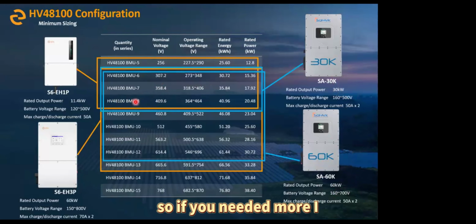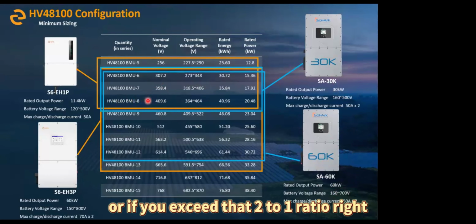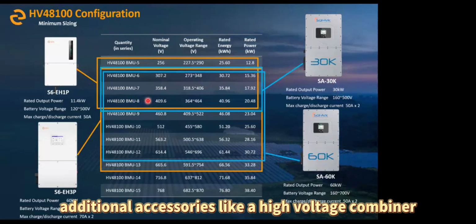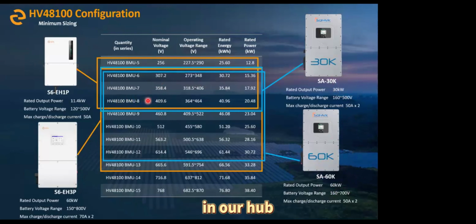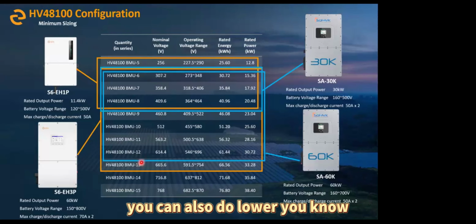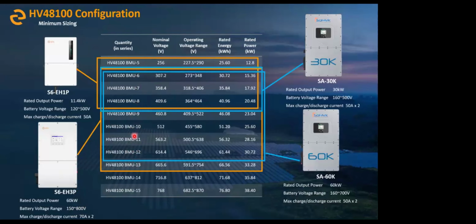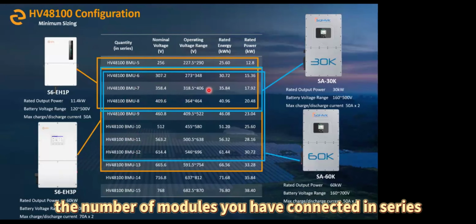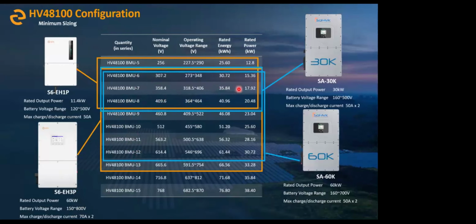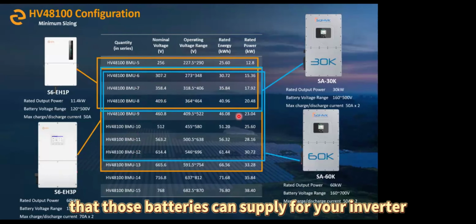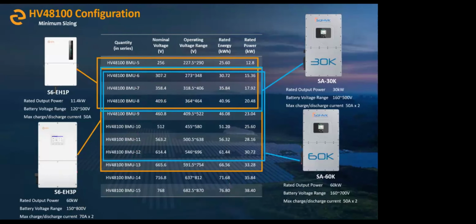If you needed more energy than what 8 modules can provide, or 40 kilowatt hours, that's totally possible - you just create another stack or group, and either land it on the other input of the inverter, or if you exceed that 2-to-1 ratio, you'd need additional accessories like a high voltage combiner or hub. With inverters that have higher input voltage ranges, you've got more flexibility in how many modules you can use. The number of modules connected in series directly affects the power output those batteries can supply for your inverter. So that's a quick glance at some of the differences there.